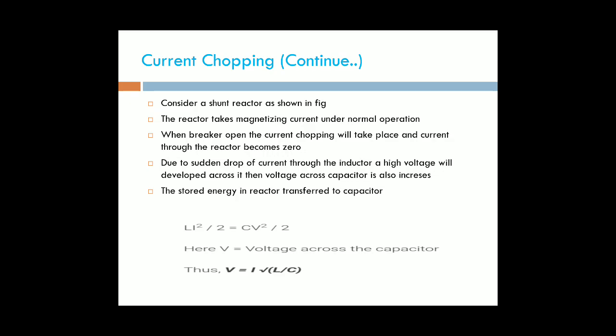Consider a shunt reactor as shown in the figure. The reactor takes the magnetizing current under normal operating conditions, that means the no fault condition. When the breaker opens, current chopping will take place and the current through the reactor becomes 0. Due to the sudden drop of current through the inductor, a high voltage will develop across it. Next, the stored energy in the inductor of the reactor is transferred to the capacitor.